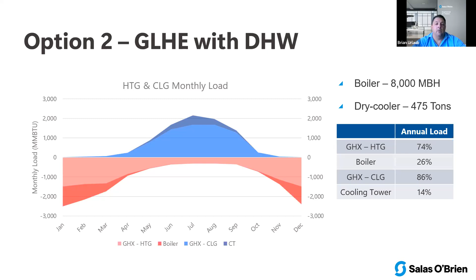And then we looked at, okay, what can sewage heat recovery do here? This is obviously a residential building. We've got a lot of wastewater. We started putting in some sewage heat recovery, again, both from a heat rejection, heat extraction component. And now we shaved another 500 MBH off the boiler, and we were at about 400 tons on the cooling side. So again, we keep whittling away at the conventional equipment by adding more technologies.